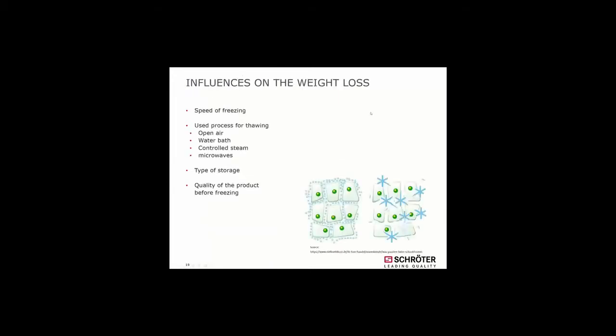What has some influence on the weight loss? First, we were speaking about the speed of the freezing. Here we have a chart or a picture where you can see a fast and a slow speed of the freezing process. If we have smaller ice crystals, as shown on the left side of the picture, the meat or the product we want to defrost is able to take the water back in, so that we have the same product as before freezing. If we use a slow freezing process, we get big ice crystals, which destroy the cell structure, and the water can drain out with proteins and, as Elna mentioned before in the presentation, with vitamins and so on.